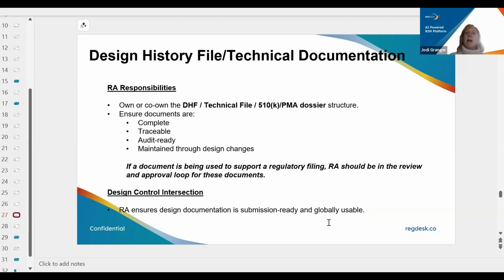In terms of the design history file and technical documentation, design history files are usually owned by R&D primarily, but regulatory plays a key role in kind of co-owning that content. The design history file and the documents contained therein are many times used as attachments or supporting evidence within your technical files, your 510(k)s, your rest of world submissions. So it's important as those design history file documents are created and modified over time that regulatory is in the loop. You need to make sure that each of those documents are complete, that they're traceable back to the source information, that they are audit ready, and that they're maintained through the design changes.